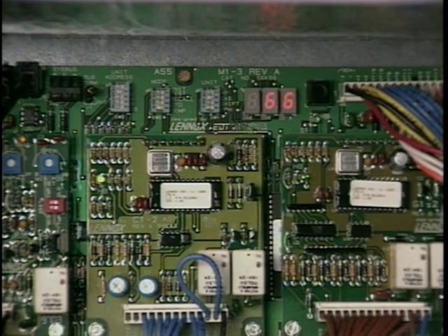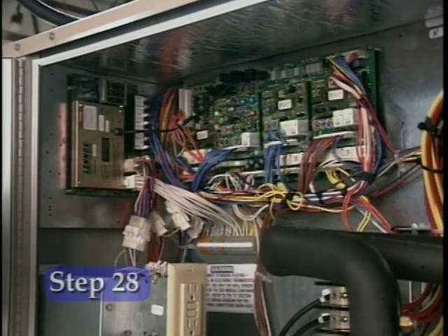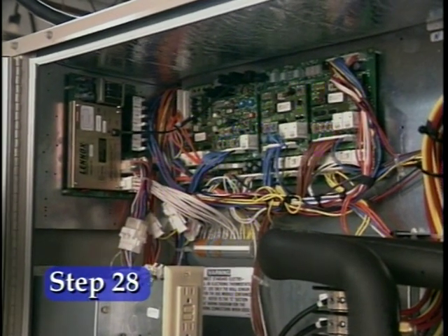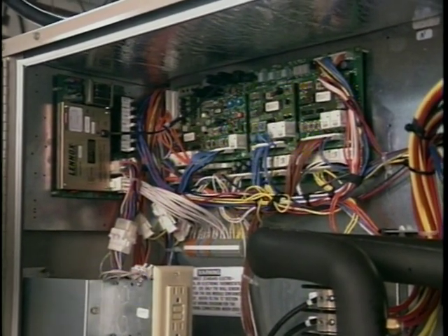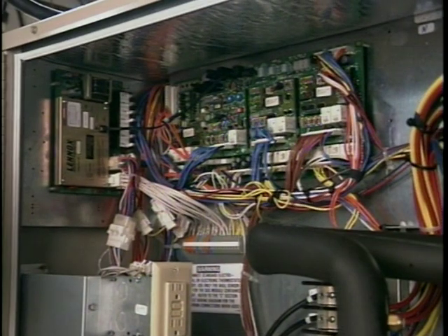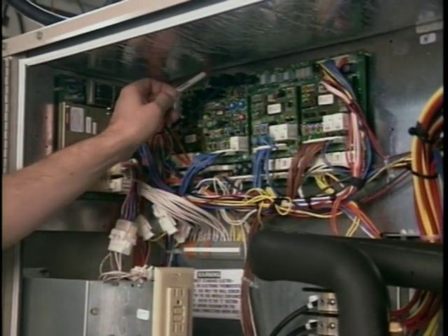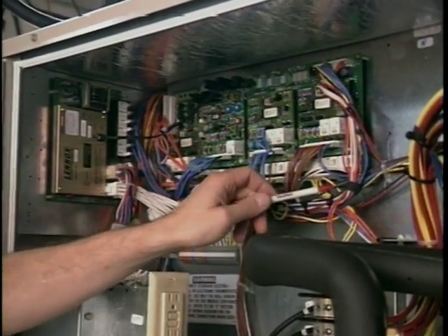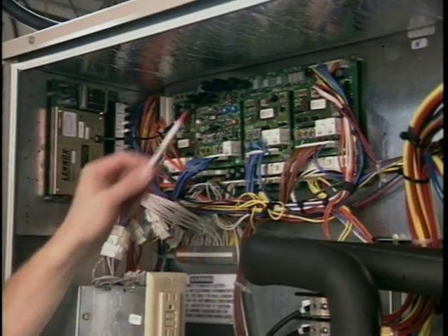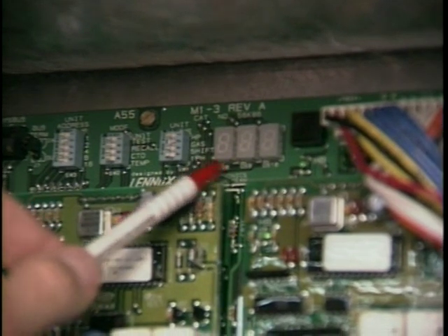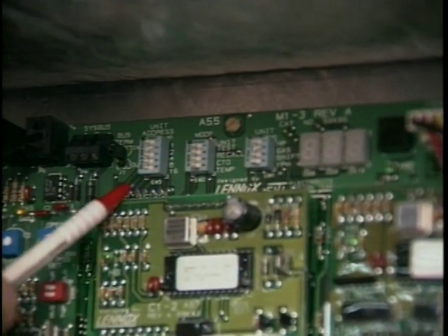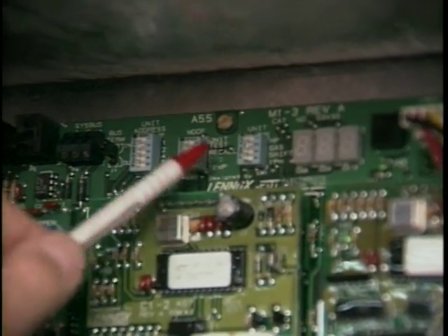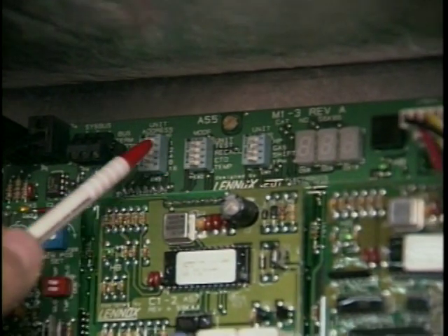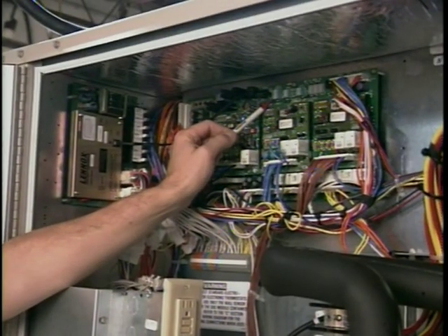This board combines the function of many separate controls into an easy-to-understand, simple-to-operate integrated modular control, the IMC. The A55 board is the main board of the IMC. It has a single display push button, a 3-character LED readout, and 3 dip switches: the unit switch, SW1, the mode switch, SW2, and the address switch, SW3.